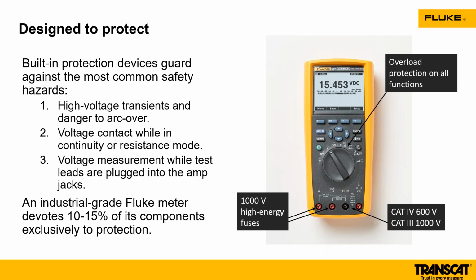When you have a Fluke meter and you may be accidentally measuring voltage and put it into continuity or resistance mode, there's enough internal protection that it's going to give you a warning, but it's not going to blow up. It's not going to cause an arc flash or an arc fault. That's a huge win. On some meters too, if you have your test leads in the wrong position, there will be a lead detect on it. The meter is smart enough to tell you, hey, you've got the test leads in amps and you have the position in volts. You need to change that.